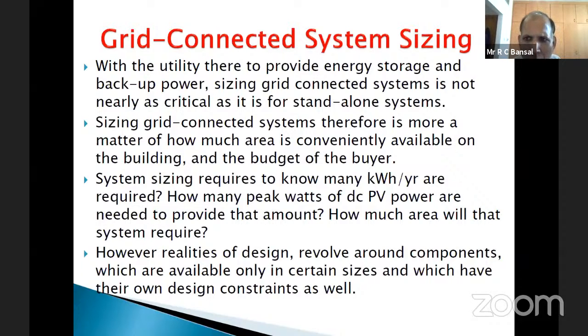Okay, so once you know how many units of electricity in a year the utility is willing to buy or have the agreement, accordingly you will plan that, okay, you have got this much area available, then how much the rating of DC power will be required. So first, from the number of units required by the utility, and then to generate that much electricity, how much space will be required, and then you can decide that this much AC power is required. From the AC power, you can convert back into the DC power rating. I gave you an example about the DC power and AC power rating.